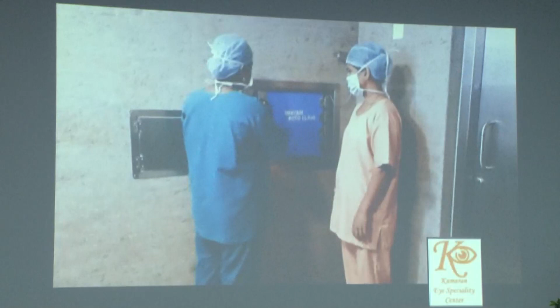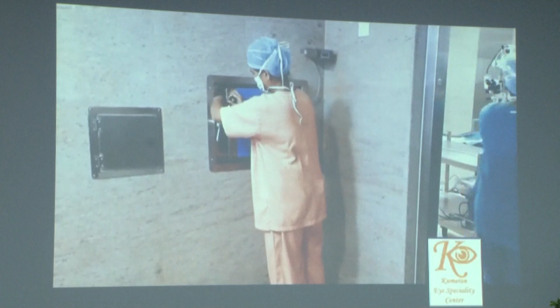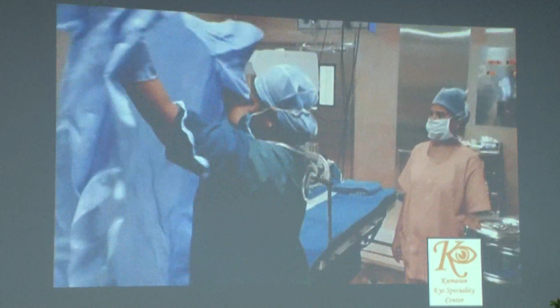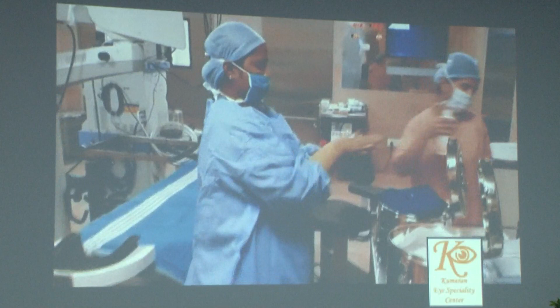Use a lint-free cloth and ensure the same part of the cloth is not used to wipe repeatedly. Once this is done, your hospital assistant then shifts all the sterile goods directly into your OT. And if you're able to keep your autoclave or the CSSD area open directly into the sterile area, it makes it very nice.